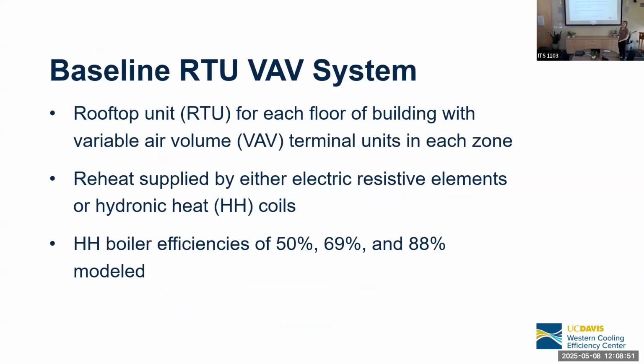And our baseline system is just a typical conventional rooftop unit with VAV terminal units. So we've got an RTU associated with each floor of the building, and the supply air, in this case, is just modulated by those VAV boxes. They have dampers that control airflow. And we had several different reheat strategies that we modeled. We started out with just electric resistive reheat. It turns out that's a pretty significant component of the energy consumption in these systems.